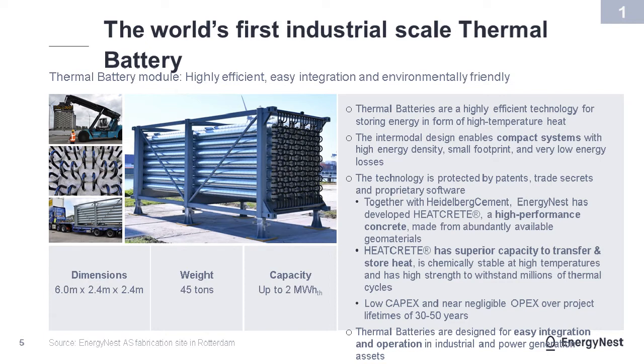So of course it's very important what we do with the heat transfer, and that means that we have to supply heat by heat transfer fluid, which typically can be a thermal oil or it can be water, steam. So you'll hear about examples of such use later on. Also this will show you actually how efficient it is in use. One module like this typically stores about 2 megawatt hours of thermal energy in relation to the operational delta T, delta temperature. And this can absolutely be compared with how much energy you can store in a container size electric battery unit. Next.